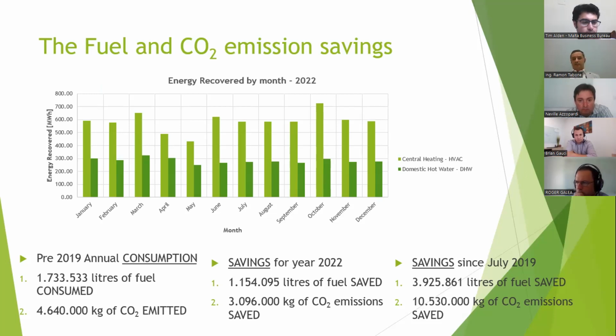As you can see, something which I anticipated in my original design in 2015, 2016, when I was studying the system, is that the demand on the hot water system for the HVAC is nearly twice the demand on the domestic hot water. This is something we didn't have originally, and it was a turning point in how we saved on fuel consumption.